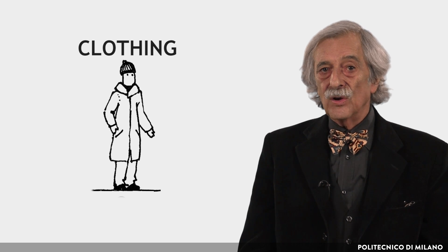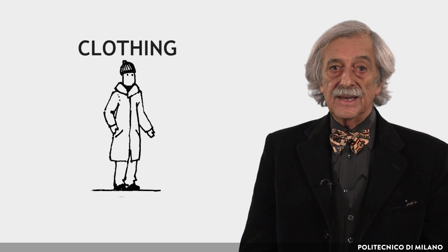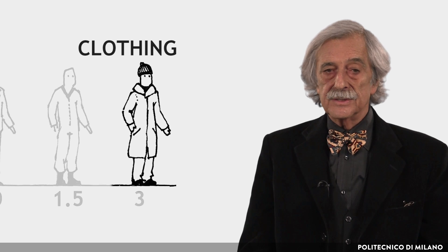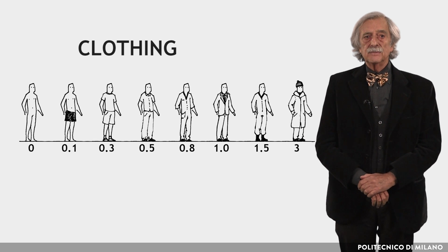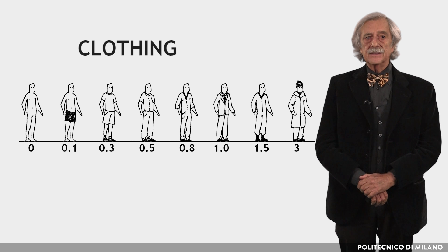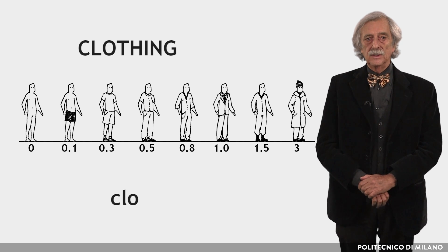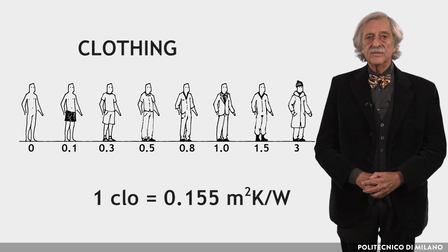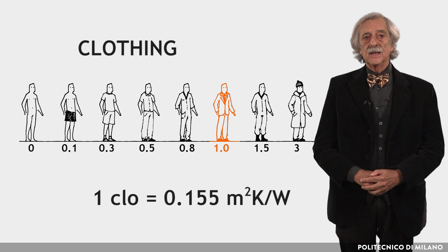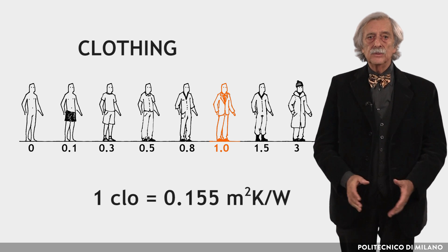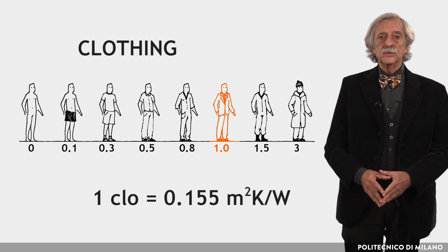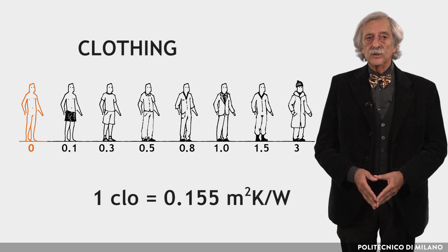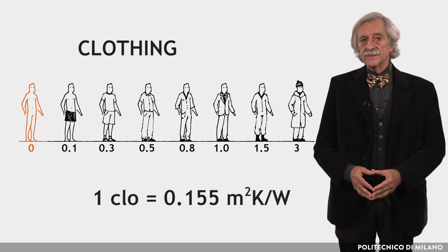The heat exchanges between the body surface and the environment depend also on the clothing we wear, as clothing acts as a thermal insulation. Thus, clothing is measured by its thermal resistance and is expressed in the unit CLO. One CLO is equal to 0.155 square meters Kelvin per watt. The value CLO = 1 corresponds to typical winter clothing. The lowest value is CLO = 0, which is a naked person.